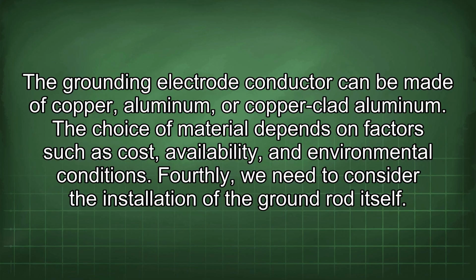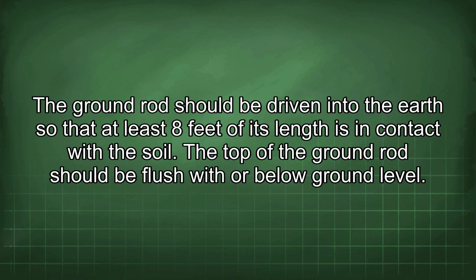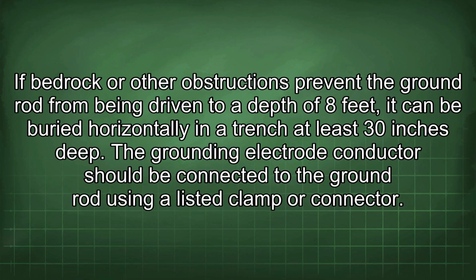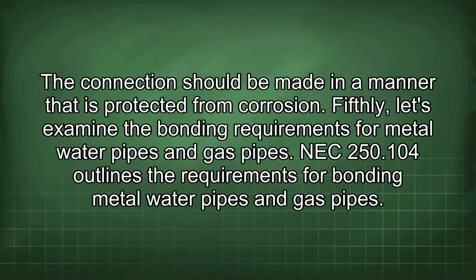Fourthly, we need to consider the installation of the ground rod itself. The ground rod should be driven into the earth so that at least 8 feet of its length is in contact with the soil. The top of the ground rod should be flush with or below ground level. If bedrock or other obstructions prevent the ground rod from being driven to a depth of 8 feet, it can be buried horizontally in a trench at least 30 inches deep. The grounding electrode conductor should be connected to the ground rod using a listed clamp or connector. The connection should be made in a manner that is protected from corrosion.